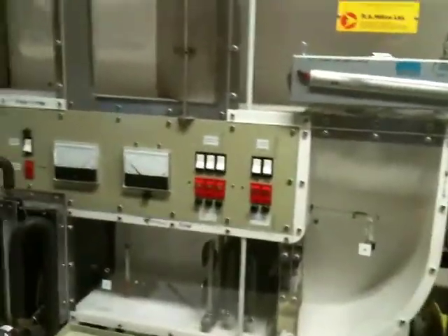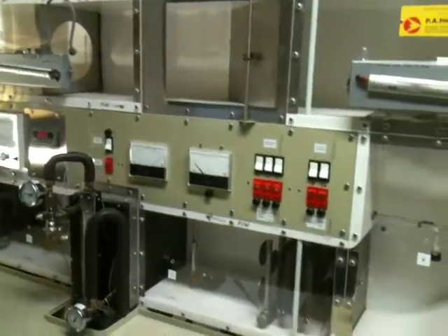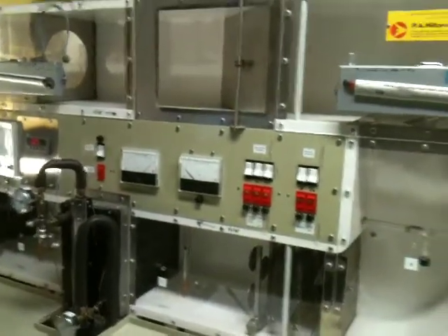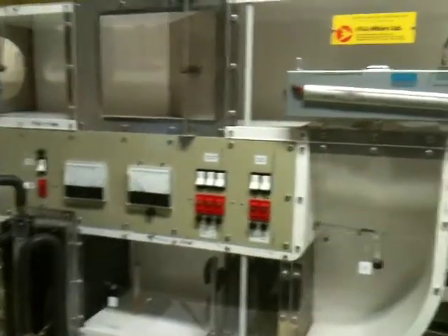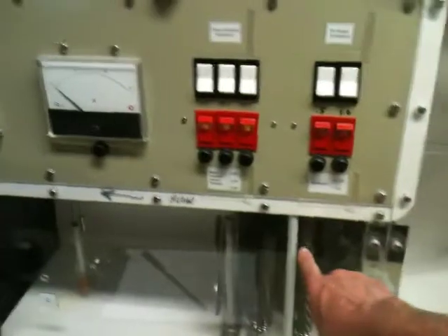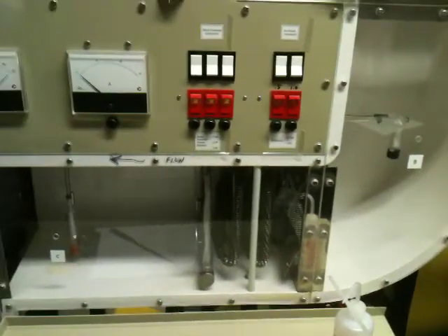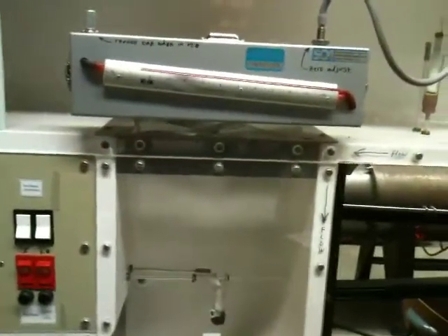In the first test, we're just going to take all the temperature readings as they are. We're not going to do any preheating or steam injection or cooling. So that's test number 1. In test number 2, we are going to turn on the preheater only. That's an electric resistance heating element. And we'll look at the effect of that on all the temperatures. Spoiler alert, it's probably not going to change the inlet temperatures very much, A and B, but it's going to increase the temperatures downstream from it.